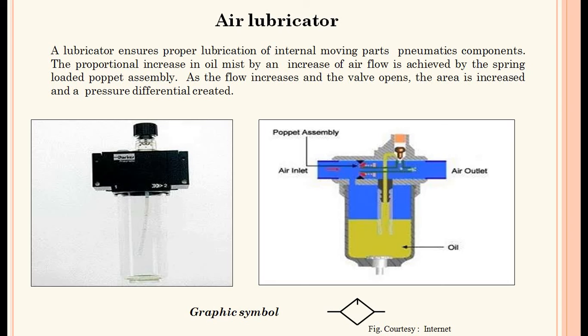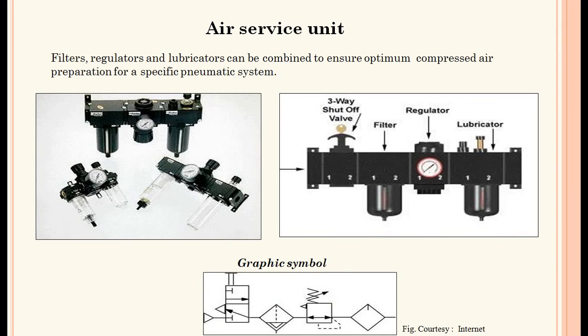Air lubricator ensures proper lubrication of internal moving parts of pneumatic systems. A proportional increase in oil mist with increasing air flow is achieved by a spring-loaded poppet assembly — as flow increases, the valve opens, increasing the area and creating a pressure difference. A photo, cut section view, and graphical symbol are shown. The filter, regulator, and lubricator combine into the air service unit, called the FRL unit, to ensure optimum compressed air preparation for the pneumatic system.